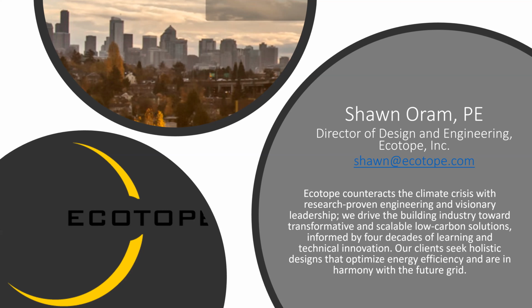There's a lot of fear that incremental transformer costs will make the project not pencil, and I just haven't seen that. We've seen a small uptick in the transformer, if any, but at the new construction level we're not seeing a huge adder like another whole 500 kVA. These are much smaller loads. For example, in this 250 unit apartment we have, the total draw is 24 kW for 250 units, so you could back into your kVA on that transformer, and that would be the adder over traditional gas. I don't think it's that big, and that's really what we're after: trying to keep these loads down with these sizing tools.